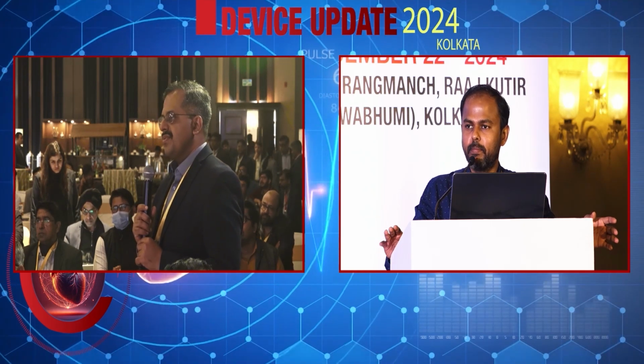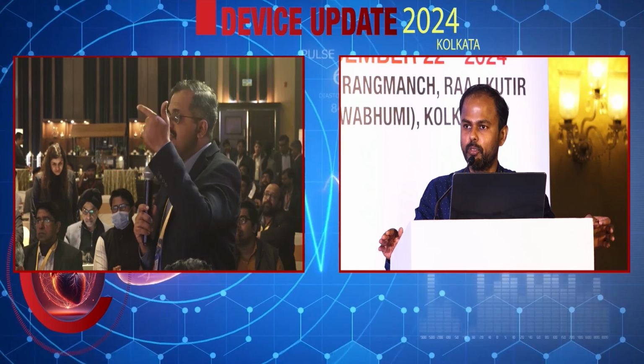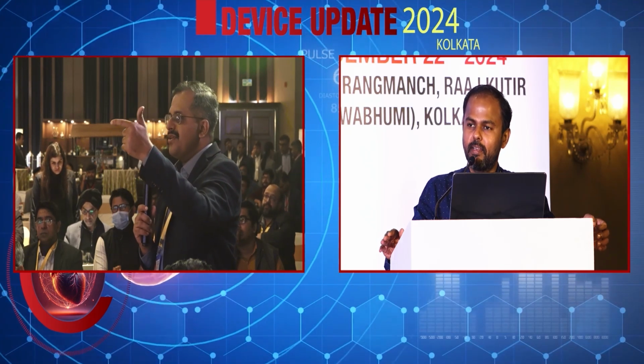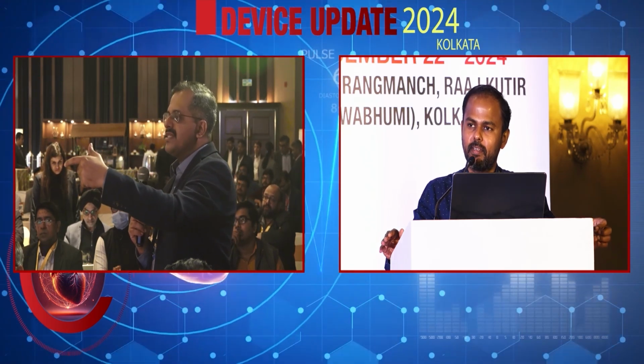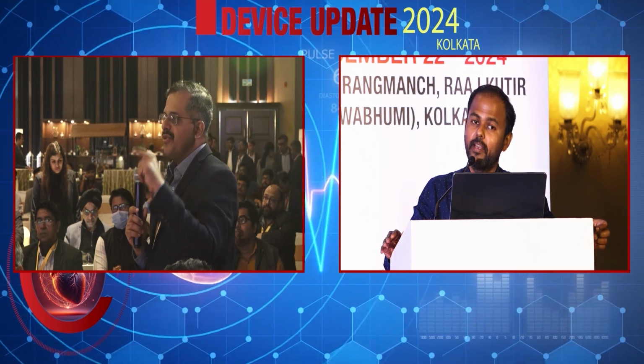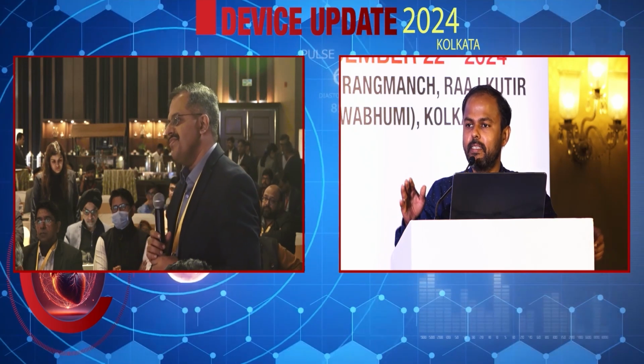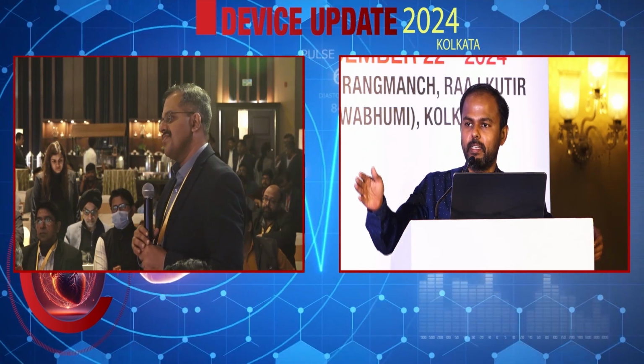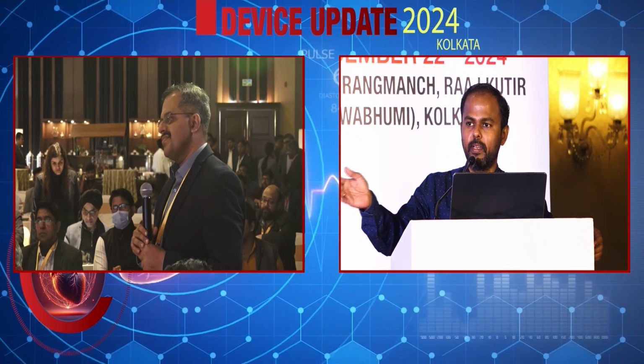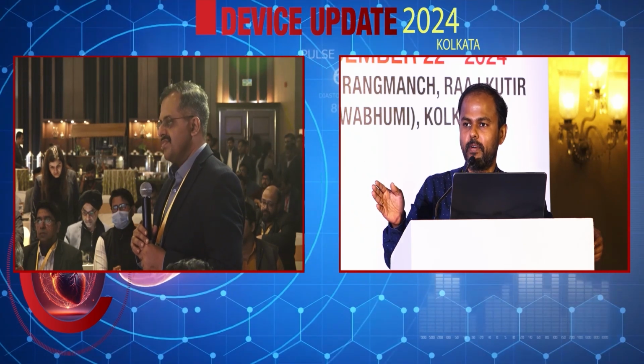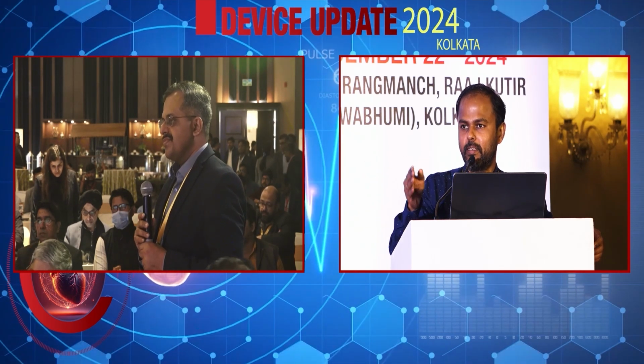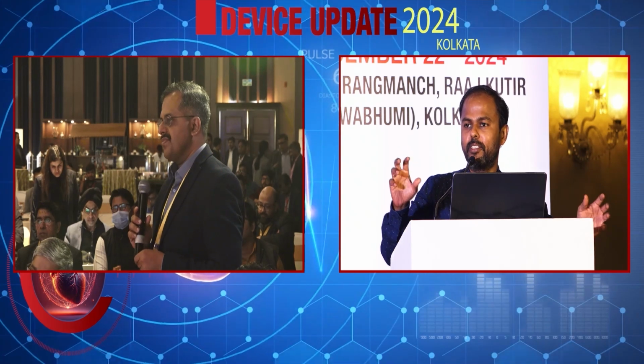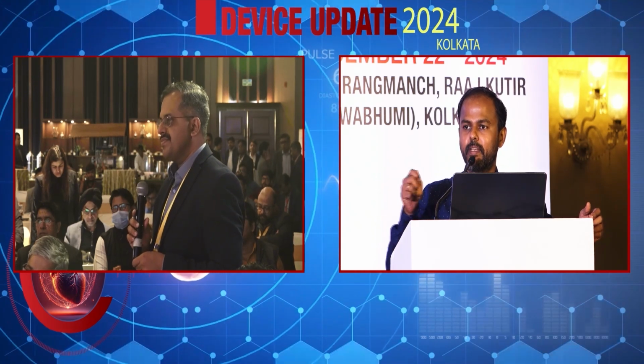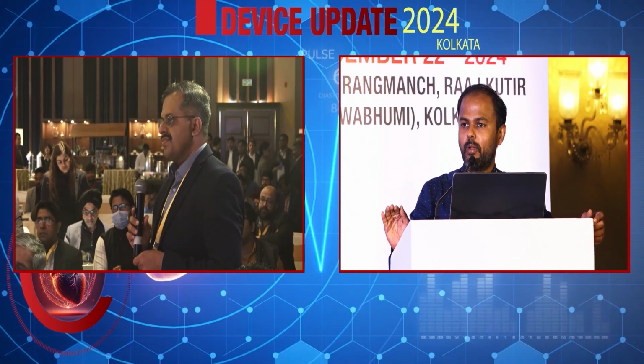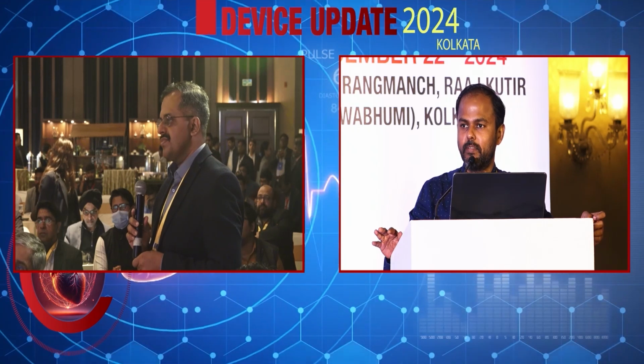Because the EGM varies depending upon the filter pattern, the device cannot see the paced QRS. The device can only see the EGM. So the EGM, whether it is in the mid septum or in the deep septum, unless it has perforated, you will not have a change in EGM morphology as compared to the baseline, because it's not like a template which is going to register it for a long time. Even if there is a micro movement, the EGM will not change, but only the QRS morphology will change.